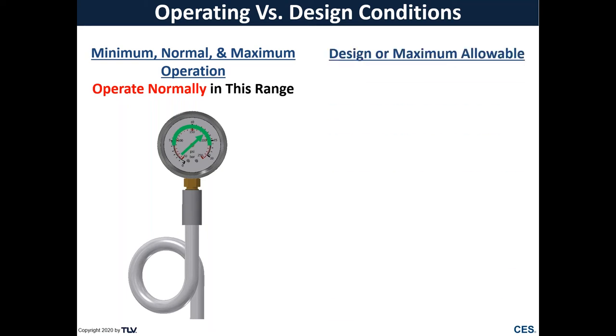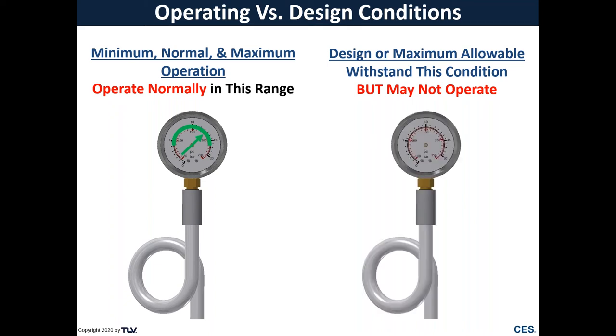Now, if we look at our design or our allowable conditions, those are conditions that the trap needs to be able to physically withstand without damage, but that trap may not be able to operate under those conditions. So that's really just a safety type condition that you need to meet. And that is going to usually be slightly or significantly higher than your normal or maximum operating conditions.